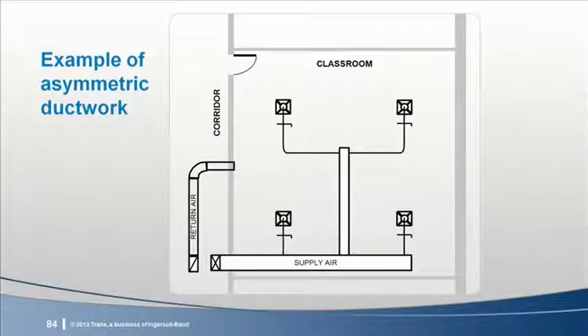In contrast, here's an example of asymmetric ductwork. The path from the supply fan to the lower 2 diffusers is shorter and straighter than the path to the upper diffusers. In this case, balancing dampers can be installed to add pressure loss to the 2 closer diffusers and force more air down the longer paths. Once balanced, if the fan operates at a constant speed, the distribution of air to these 4 diffusers remains essentially the same during operation. But with a variable speed fan, the pressure losses through the longer and shorter paths do not necessarily remain proportional as the fan speed changes.